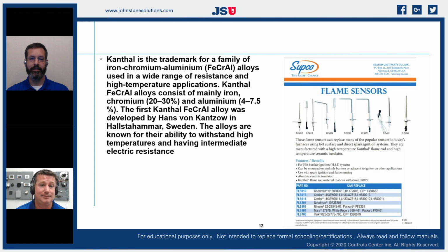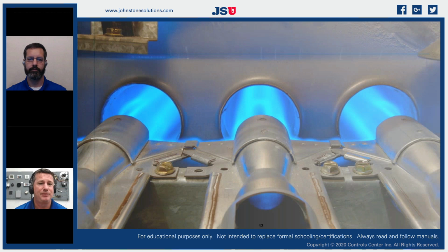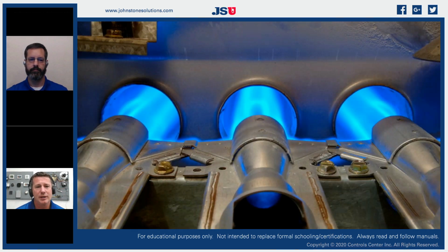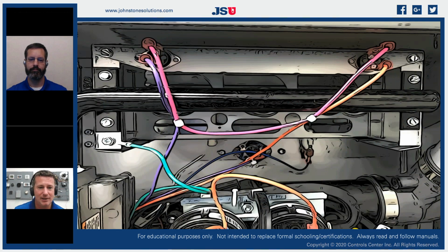So we clean that. And anything that's coated on there is going to act as an electrical insulator. Any kind of insulation is going to stop the flow of those electrons that we need. It's all about the flow of electrons. If I add an insulator to a conductor, I'm going to slow down my flow of electrons. So the next time that you are working on a furnace, doing a service, and cleaning that flame rod and making sure it's nice and clean so that it can be a sensor for our flame, just remember it's one of two important parts in that entire circuit.